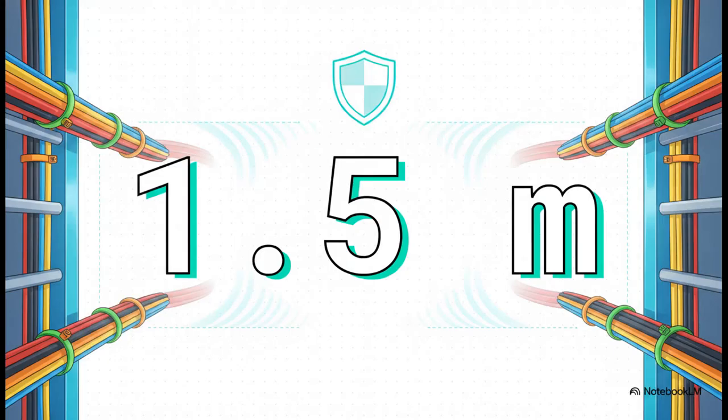And when you're installing these cables, you obviously need to tie them down. 1.5 meters. That's your magic number right here. Just remember the rhyme, 1.5 keeps it alive when you're dealing with excessive movement. You must fasten insulated conductors and cables at intervals not exceeding 1.5 meters where movement could be caused by fault current magnetic forces. This is also, by the way, the maximum support interval when Type TCER cable transitions out of a tray.